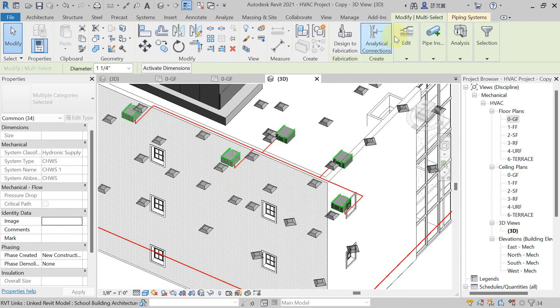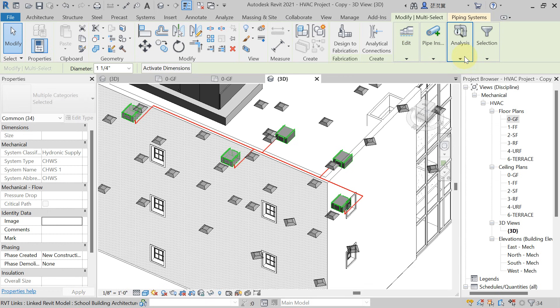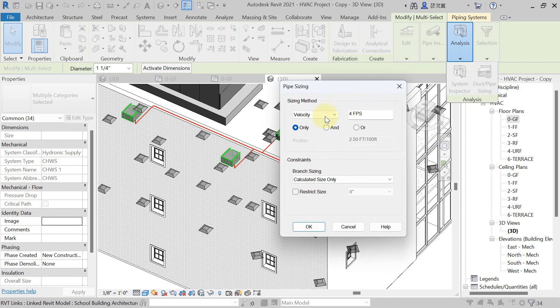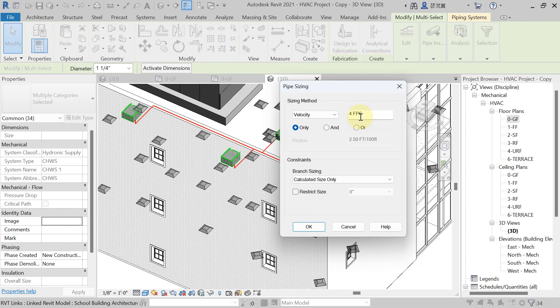Now in the Modify tab, in the Analysis panel, you will get the option of Duct or Pipe Sizing — hit on that. For chilled water pipe sizing, we always have to maintain 4 fps velocity. So write down 4 fps here.